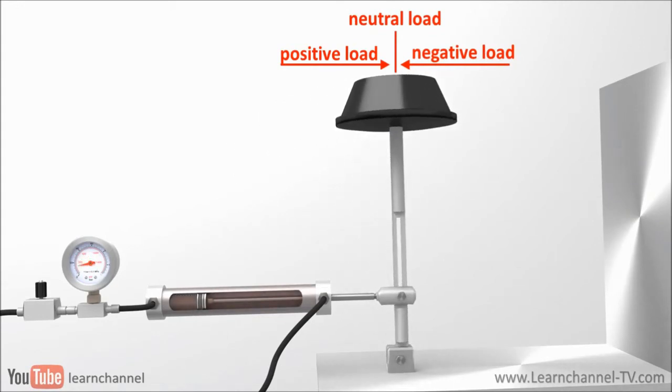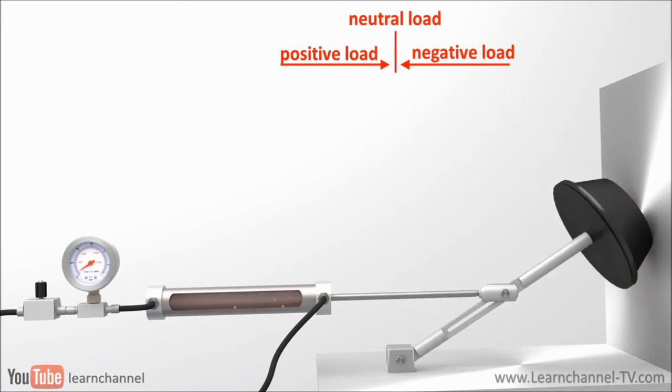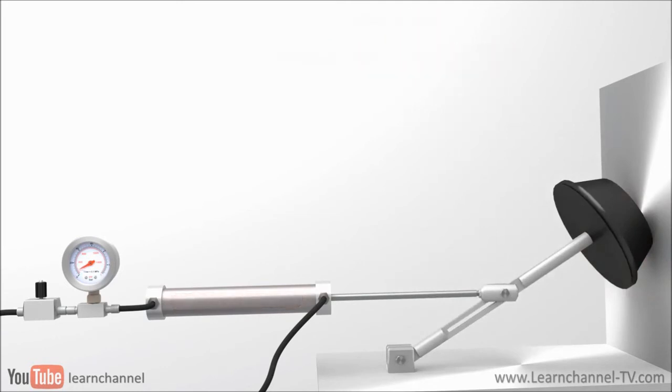The advantage of meter in is that it is very accurate to a positive load. The problem here is, when the load goes over center, the load becomes negative or overruns and can no longer be controlled by the cylinder. Besides the risk of damage, you get cavitation when the load plumps down and air is sucked in.